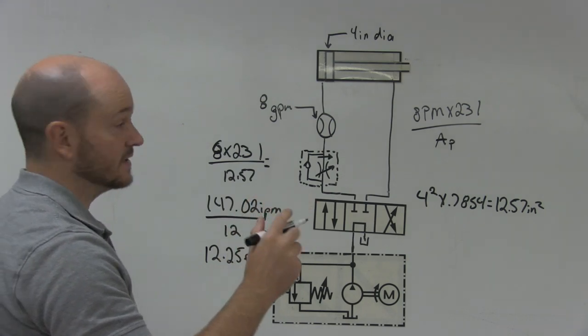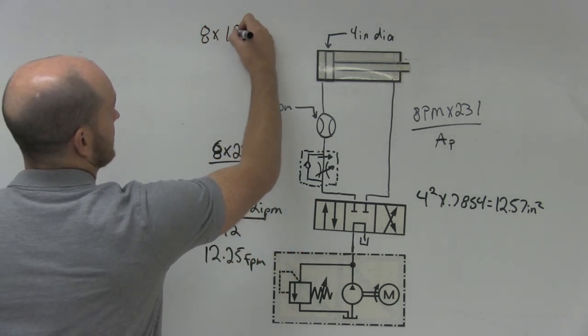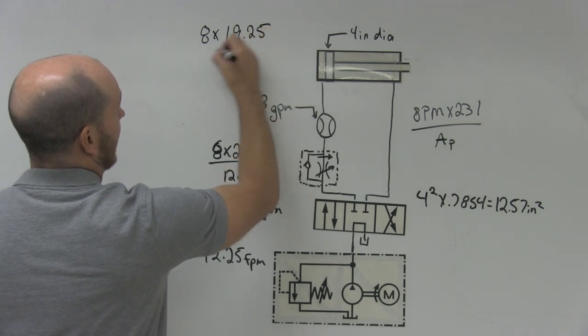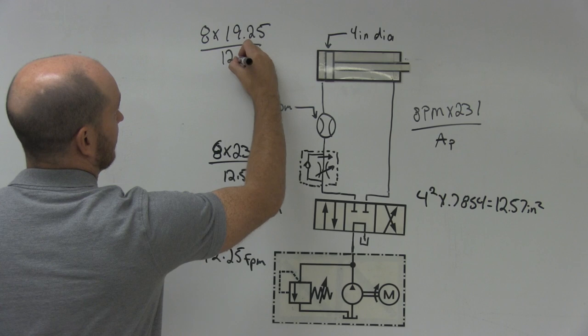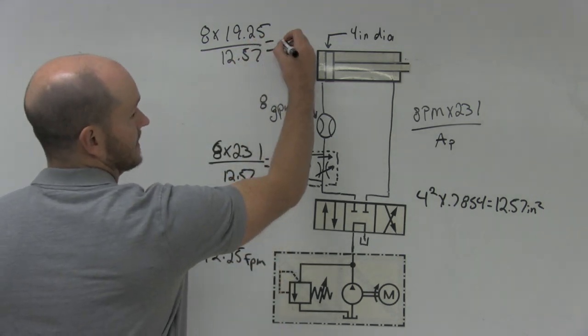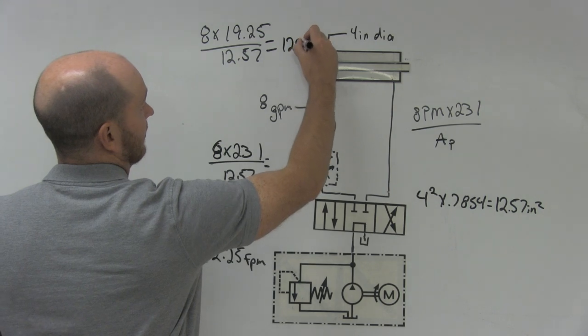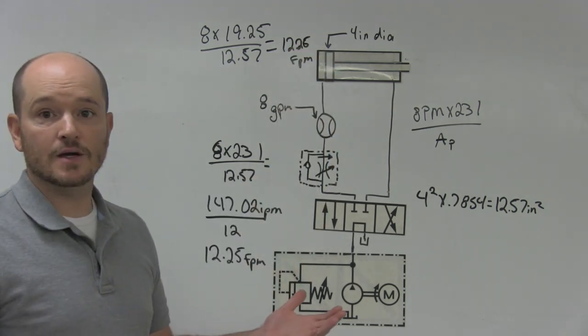Or, you could run it through this formula here. 8 times 19.25 divided by, again, the area, which was 12.57. So this answer would still come out to be 12.25 feet per minute. And this is how you calculate it out.